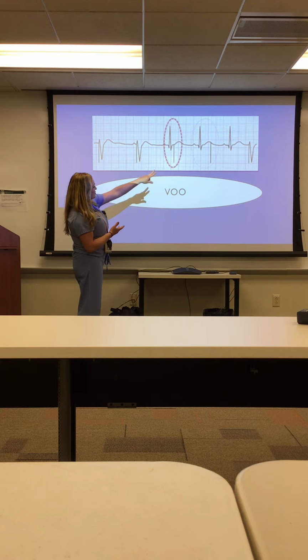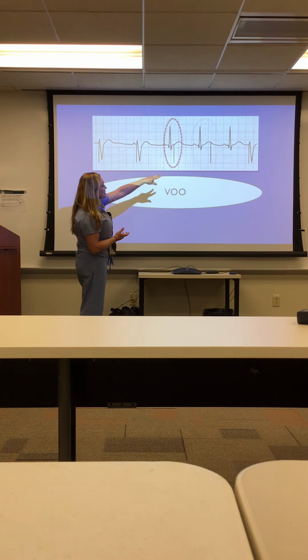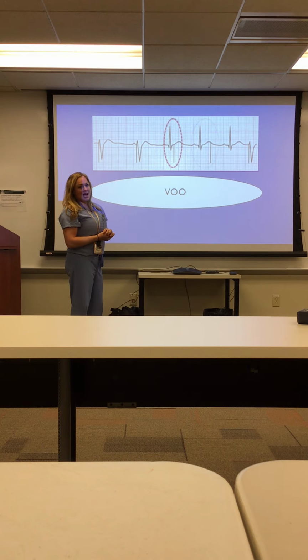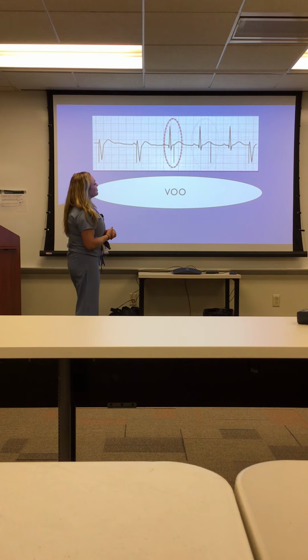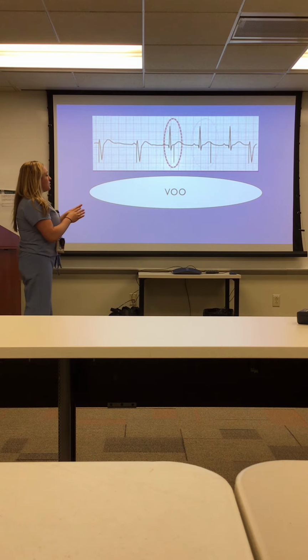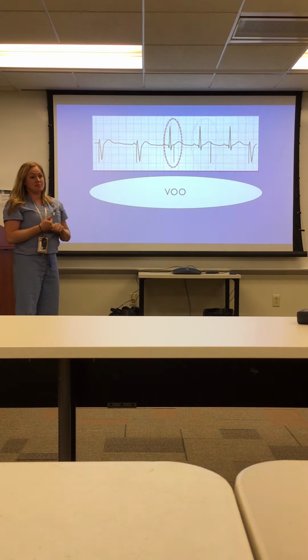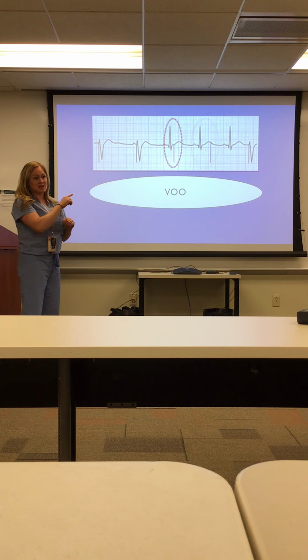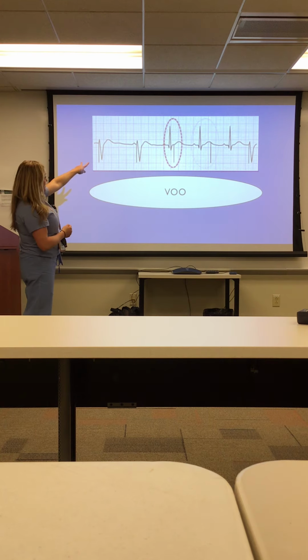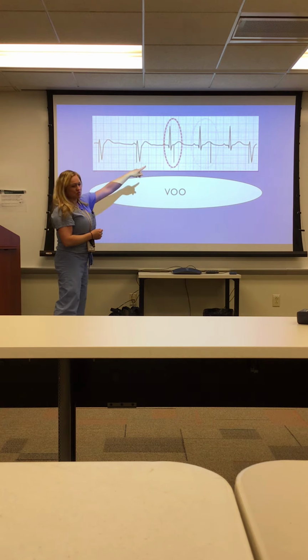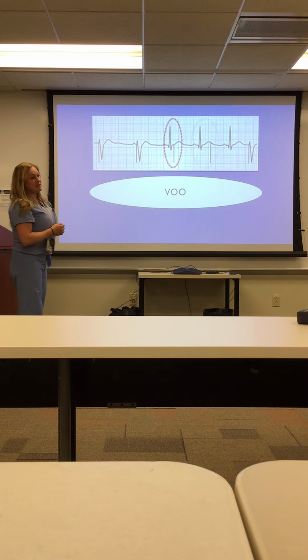So we see some irregular beats coming through, and they're not capturing because these are in repolarization. You're not going to get any beats to capture if you're in the T wave, and you don't want to be in the T wave. Typically, if you're in this mode, you want to make sure that you're at least 10 beats a minute above whatever their intrinsic rate is, so you don't have these competitive beats coming through, because that's when you run into shocking on a T wave, potentially. You've got to make sure that you're overdriving that rate, and you see these beats marching through the whole time without these intrinsics.